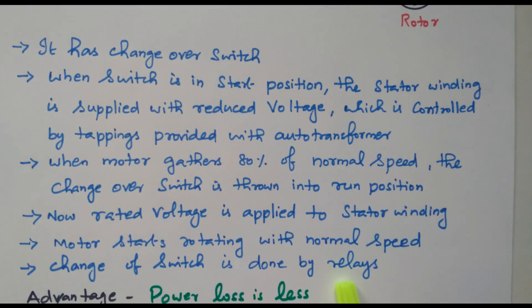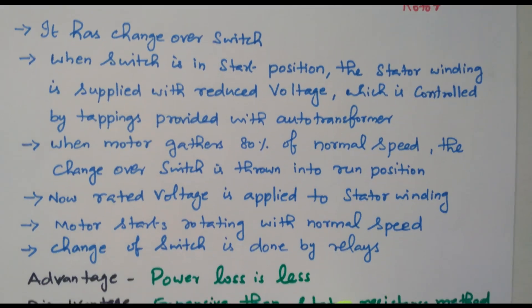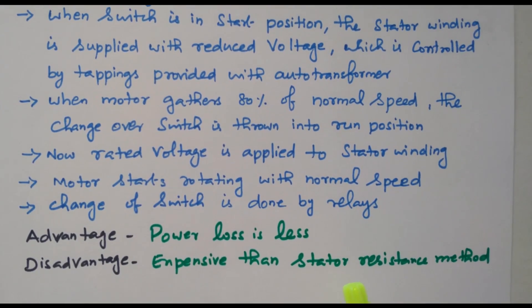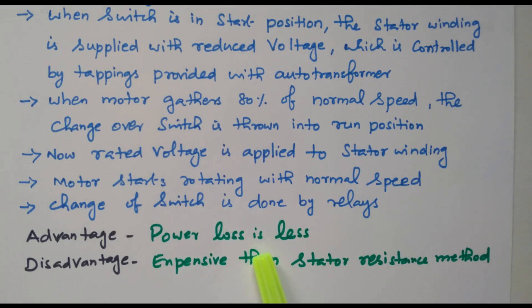In this method, the auto-transformer is used to apply the reduced voltage to the stator so that the current taken by the stator is also reduced. The main advantage of this method is that power loss is less. In the stator-resistance method, power is lost, but here power is not lost. However, a disadvantage is that this method is expensive. The stator-resistance method is very cheap — only one set of resistors is needed — but here we need an auto-transformer, which is more expensive.